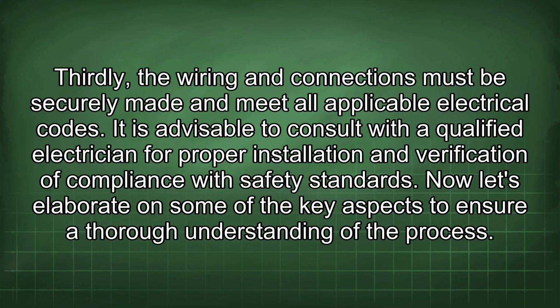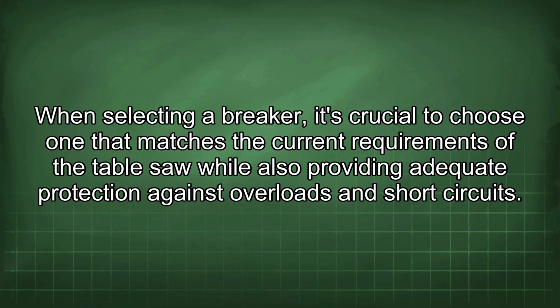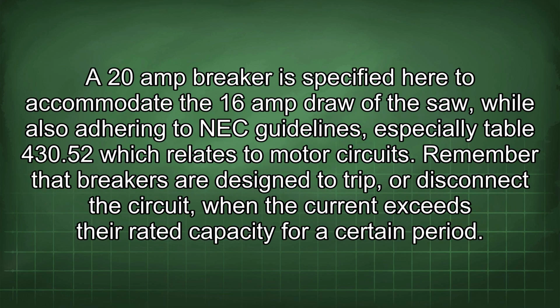Now let's elaborate on some of the key aspects to ensure a thorough understanding of the process. When selecting a breaker, it's crucial to choose one that matches the current requirements of the table saw while also providing adequate protection against overloads and short circuits. A 20 amp breaker is specified here to accommodate the 16 amp draw of the saw, while also adhering to NEC guidelines, especially Table 430.52, which relates to motor circuits.